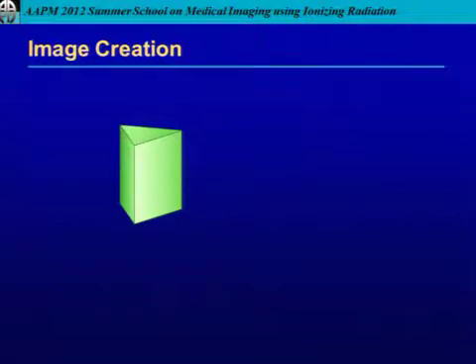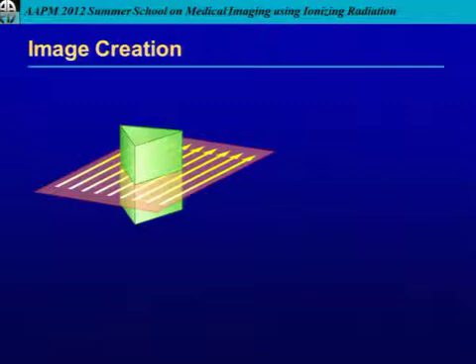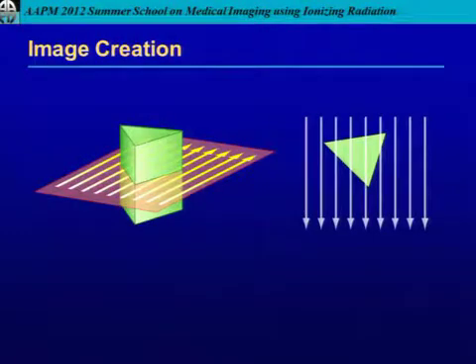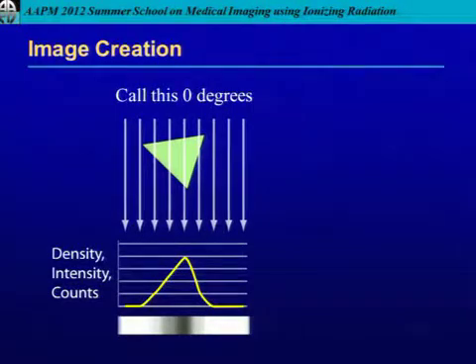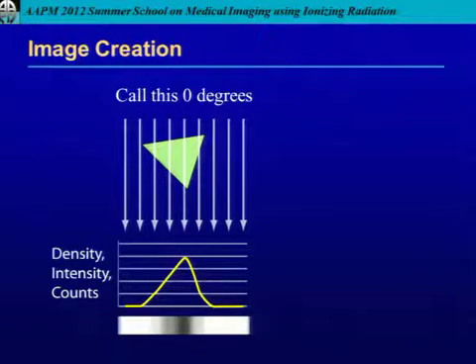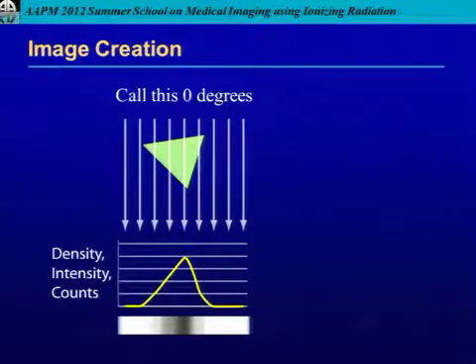What I'm going to walk through next is a graphical illustration of how it's possible to create a cross-sectional image just by looking at an object from different angles. We have a simple three-dimensional triangle, and we shoot X-rays through it. Viewed from the top, we start at zero degrees — we get a measurement of transmission or intensity, which we can display as a plot or convert into a grayscale. The width of the grayscale is just arbitrary, sized so you can see it from the back.